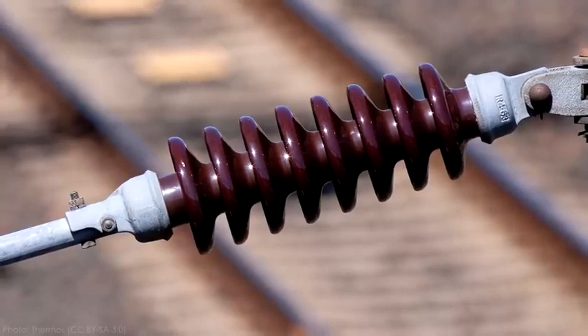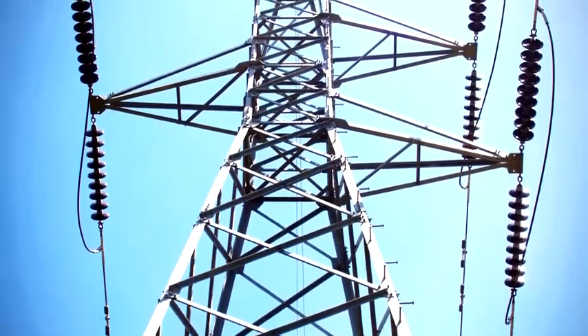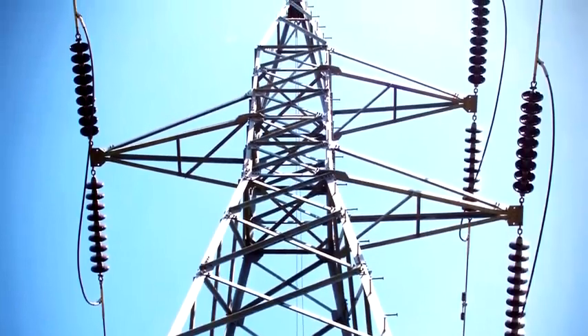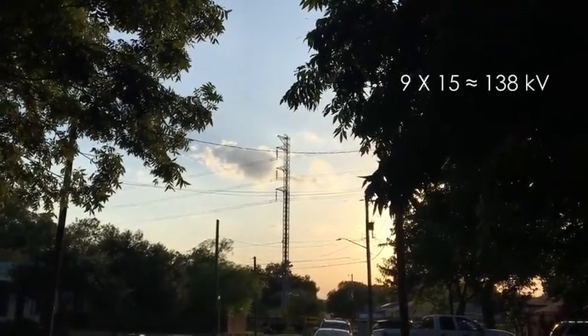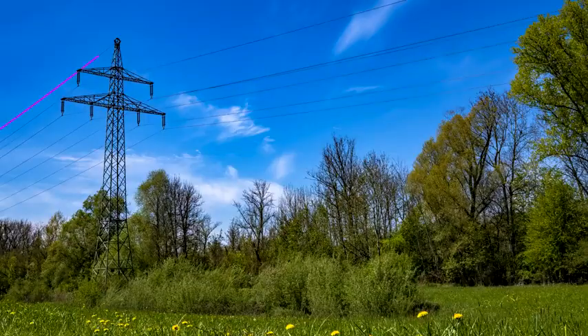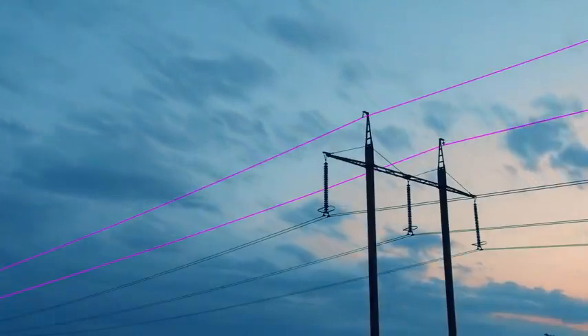The conductors are connected to each tower through long insulators to keep enough distance between energized lines and grounded pylons. These insulators are normally made from ceramic discs so that if they get wet, electricity leakage has to take a much longer path to ground. These discs are somewhat standardized, so this is an easy way to get a rough guess of a transmission line's voltage — just multiply the number of discs by 15. For example, a line near my house has 9 discs on each insulator, and I know it's a 138 kilovolt line. You'll also often see smaller conductors running along the top of transmission lines — these static or shield wires aren't carrying any current; they're there to protect the main conductors against lightning strikes.